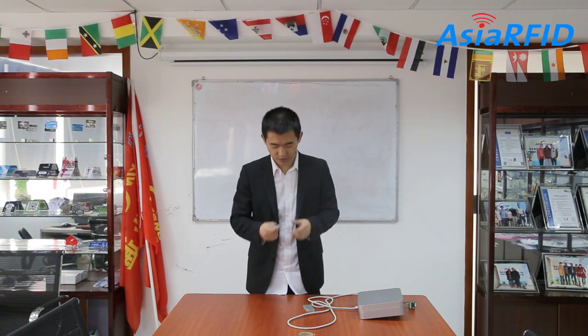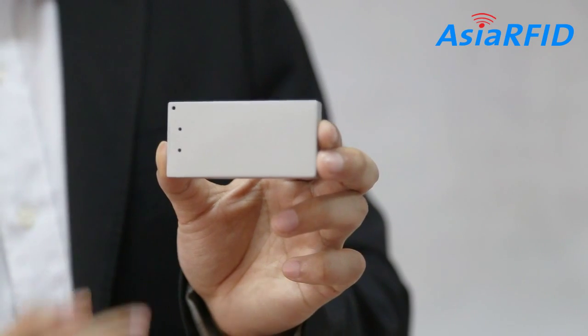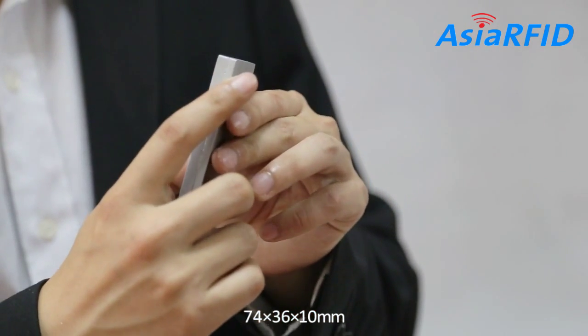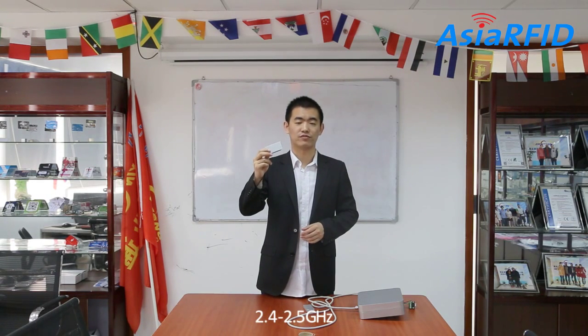First, it's the Active SenseTag. It's so small and light. Its dimension is 74 x 36 x 10 mm and the working frequency is 2.4 to 2.5 GHz. It can detect the temperature from below 0 to about 80 degrees and the humidity from 0 to 100%. The detection range is about 100 square meters and from top to bottom to 3 meters.